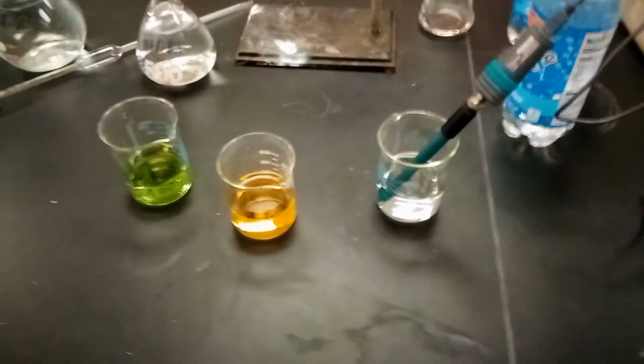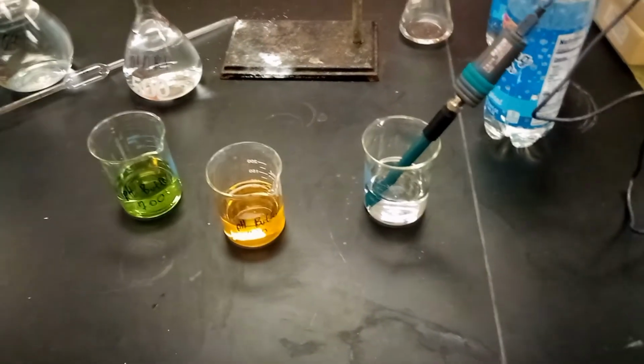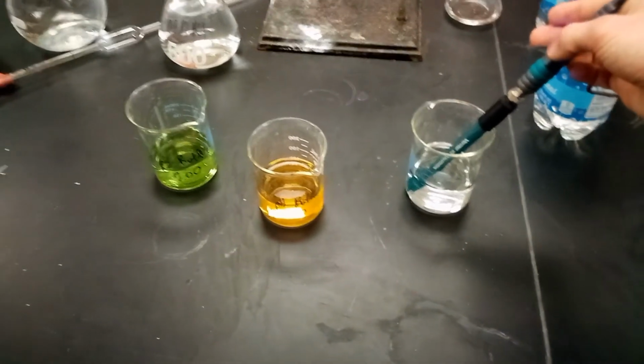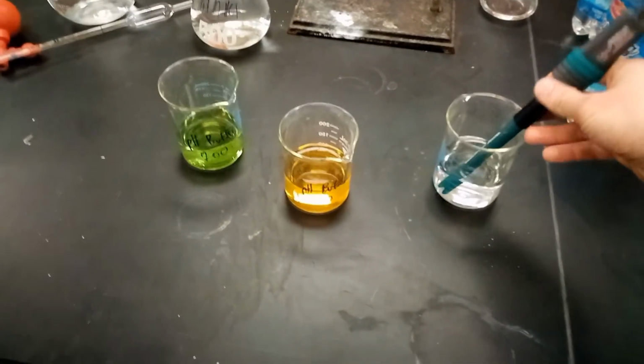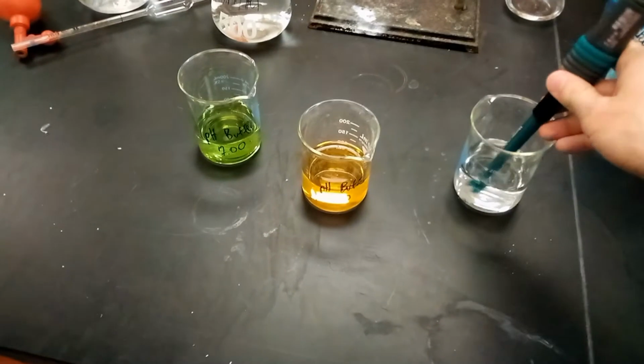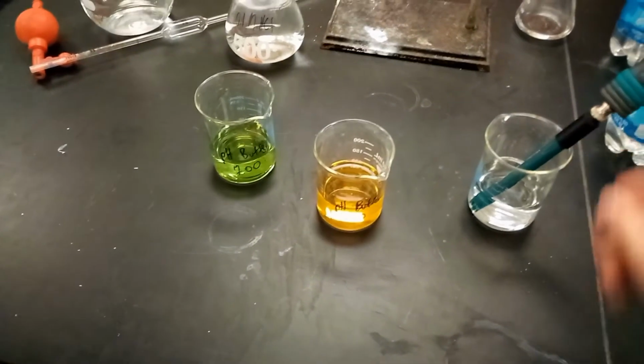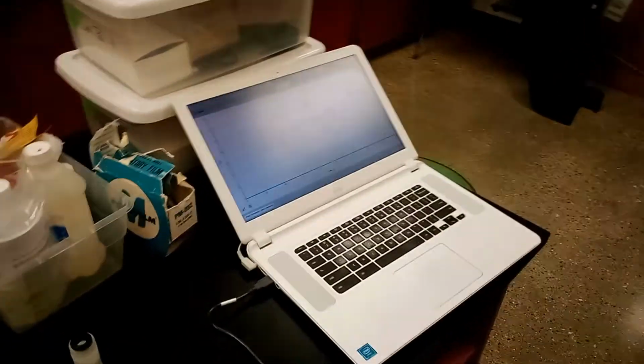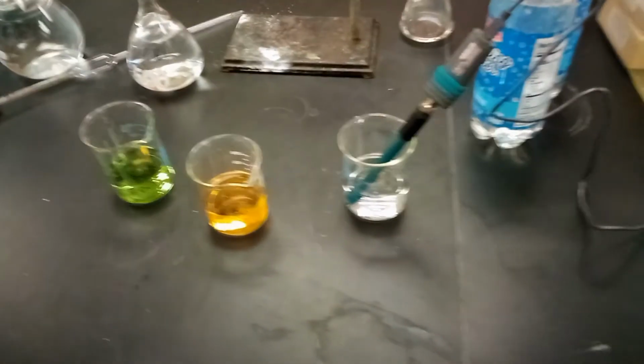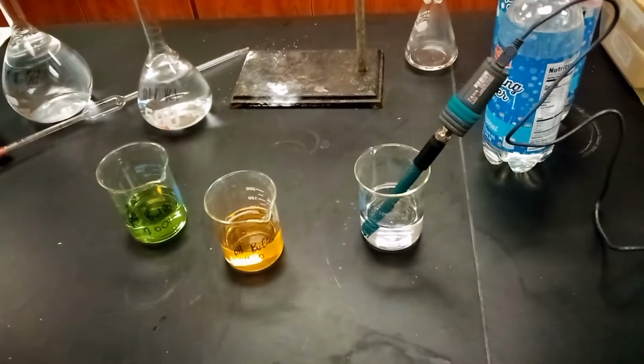So we're going to be doing a quick video on how to calibrate this pH probe, the Vernier pH electrode probe. So we have it in some distilled water right now, and we have it hooked up to Graphical Analysis on our computer over here. It's a 2-point calibration system.